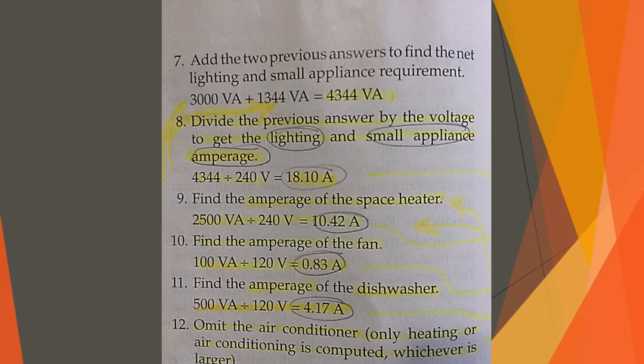Step 8, divide the previous answer by the voltage to get the lighting and small appliance amperage, which is 4,344 divided by 240 volts, giving us 18.10 amps. Step 9, find the amperage for the space heater, which in this case is 2500 VAs divided by 240 volts, which gives us 10.42 amps. Step 10, find the amperage for the fan, or 100 VAs divided by 120 volts, or 0.83 amps. Step 11, find the amperage for the dishwasher, which is 500 VAs divided by 120 volts, or 4.17 amps.